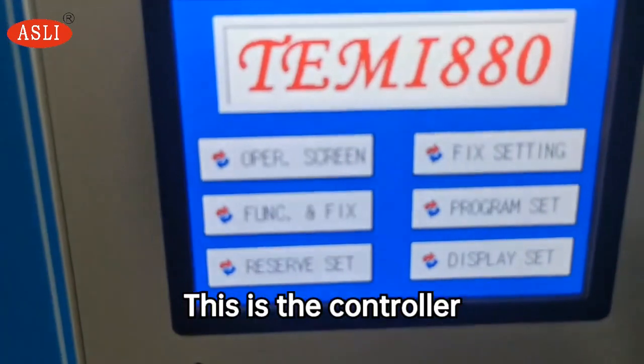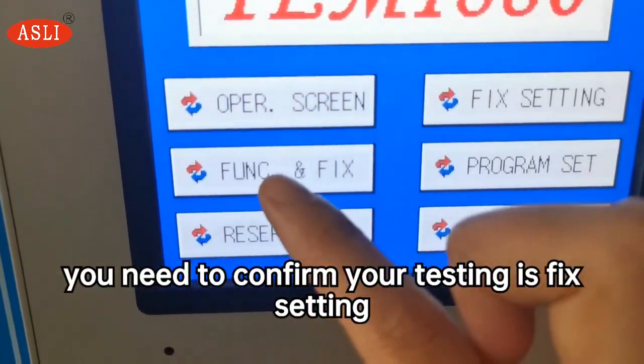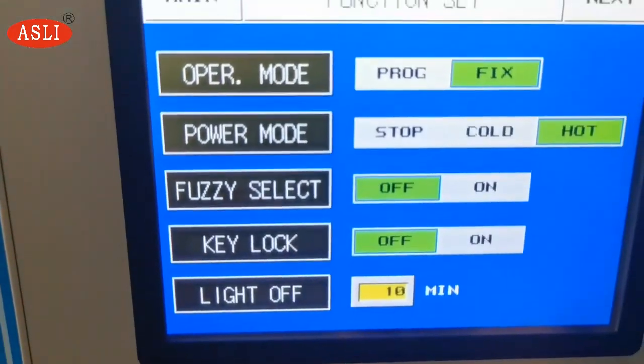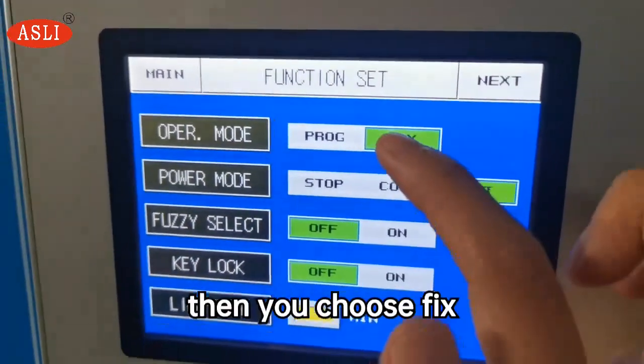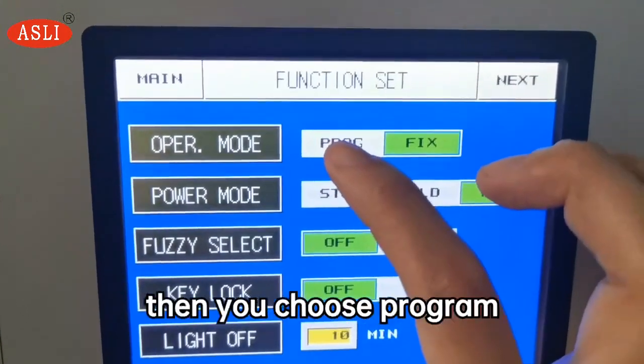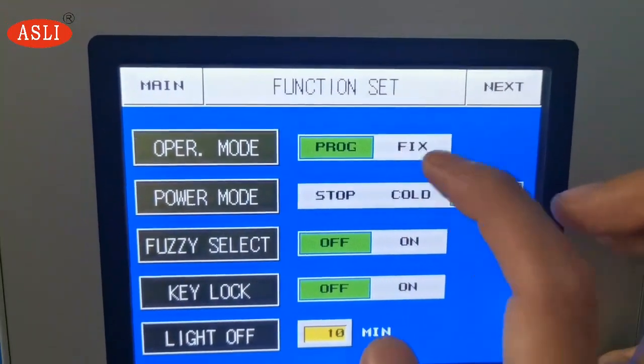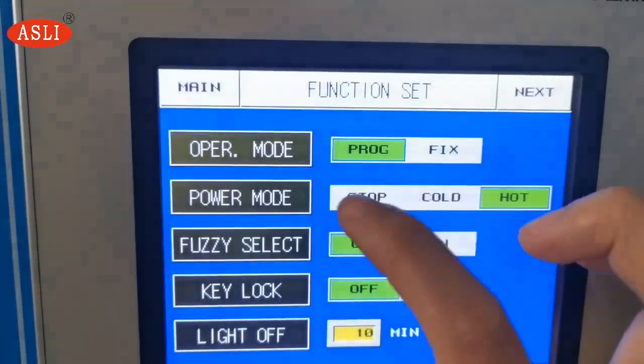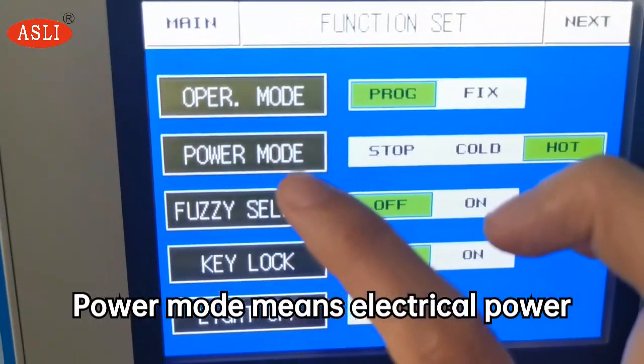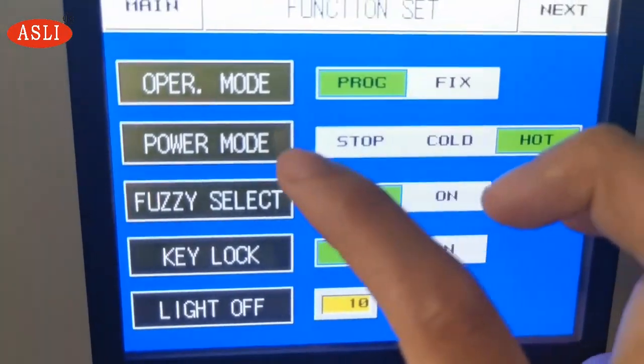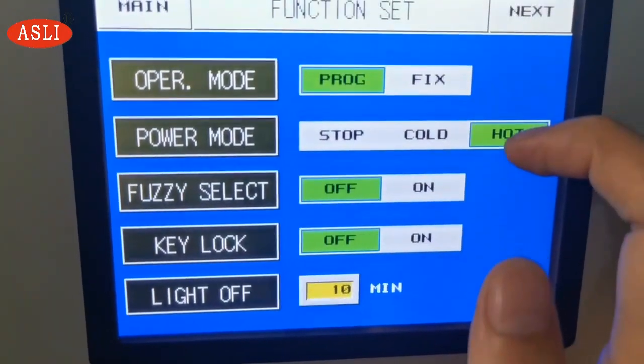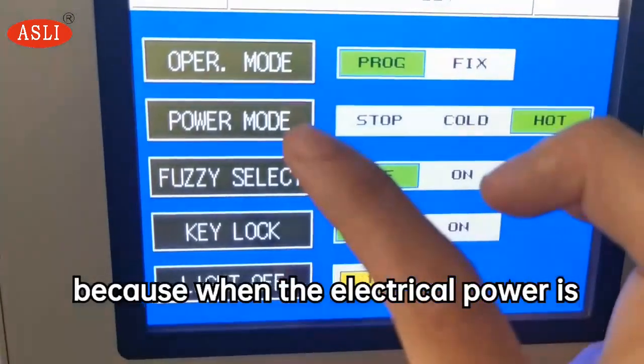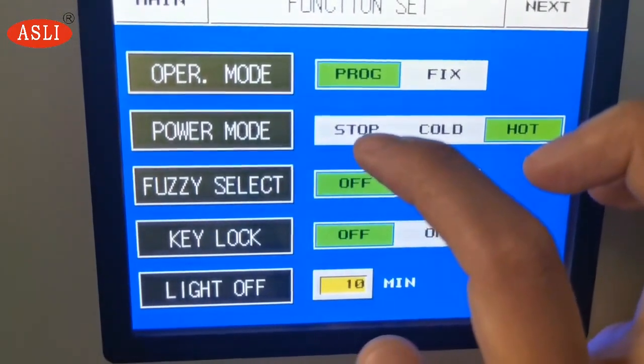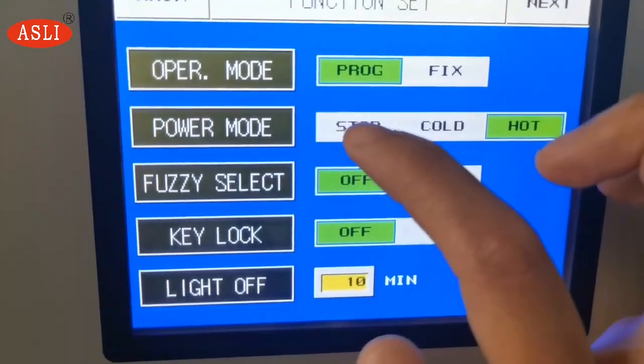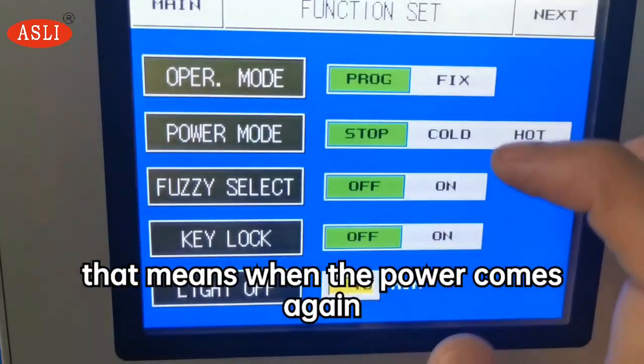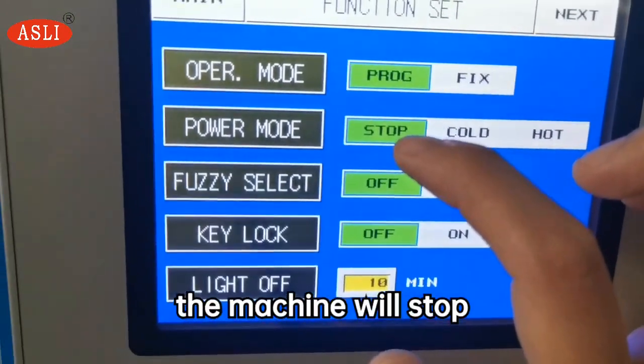This is the controller. First, you need to confirm whether your testing is fixed setting or program setting. If it is fixed setting, then you choose fixed. If it is program setting, then you choose program. Power mode. Power mode means electrical power: stop, cold, hot. We suggest to use hot, because of when the electrical power is suddenly lost. If we choose stop, that means when the power comes again, the machine will stop.